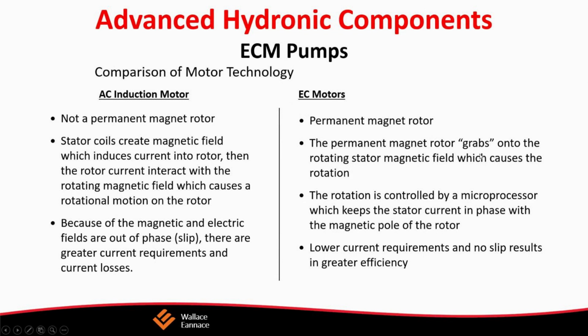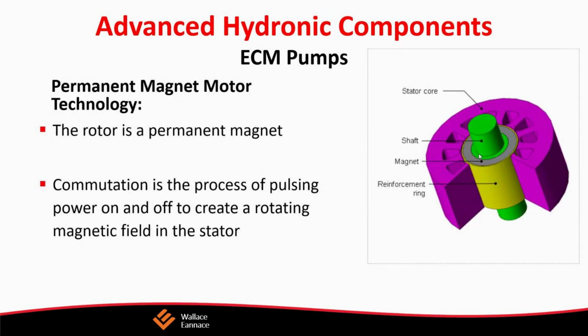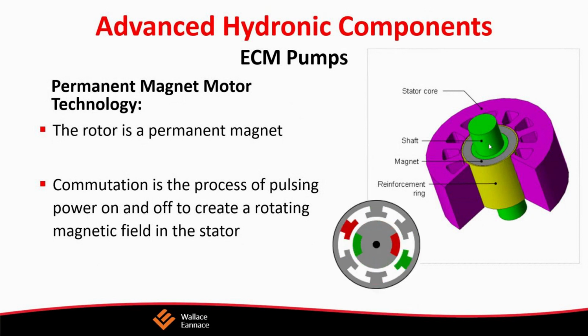ECM motors, what makes them different from standard pumps? Well, it really comes down to the motor. These motors will look the same as your standard induction motors, but the construction of the motor is completely different. Most of the pumps that you see, especially wet rotor pumps, are AC induction motors. They don't have a permanent magnet. The stator coils create a magnetic field which induces current into the rotor, and the rotor current interacts with the rotating magnetic field, which causes a rotation motion in the rotor. Because the magnetic and electrical fields are out of phase, there's a little slip, and you need greater currents and greater current losses.